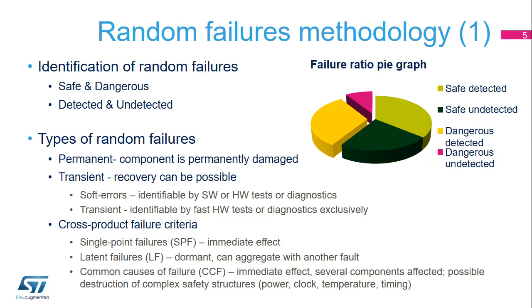The safe failure fraction, or SFF, is the ratio of the rate of safe failures — including the rate of detected dangerous failures — to the total failure rate of safe failures as well as detected and undetected dangerous failures. The diagnostic coverage, or DC, is the ratio of the probability of detected dangerous failures to the probability of all the dangerous failures.